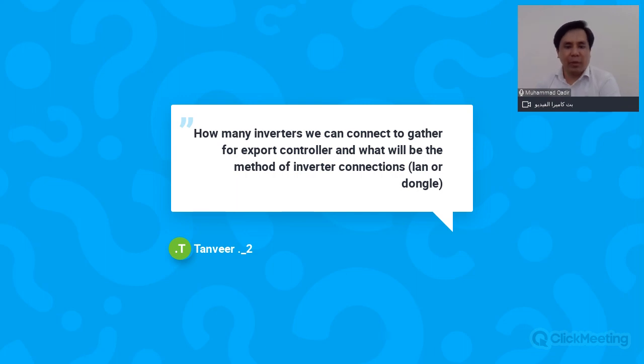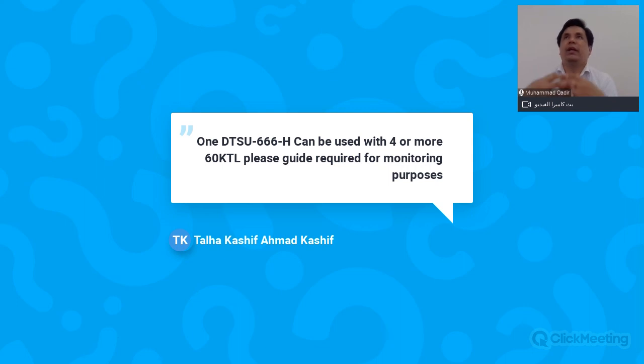Tanveer is asking how many inverters we can connect together for export controller, and what will be the method of inverter connection, LAN or dongle. As I said earlier, there can be multiple scenarios: a single inverter, multiple inverters, and more than 10 inverters. If you are using up to 10 inverters, you can use a smart dongle, and you must be using one of the smaller range of inverters that is compatible with the smart dongle.